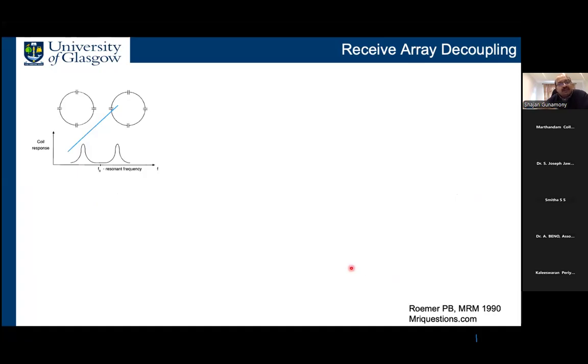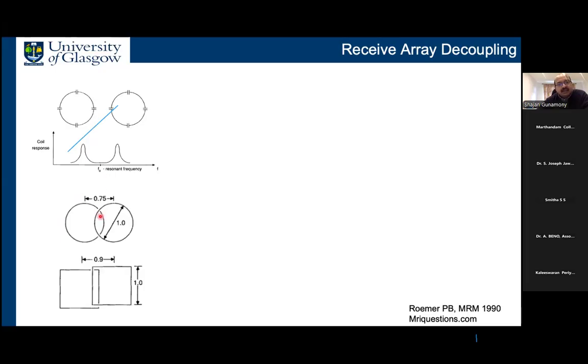So Roemer also proposed a method to build these kinds of coils. As I said, the coils are all resonant circuits. They are tuned to the Larmor frequency. Suppose we have 2 coils. They are tuned to the same frequency. And if you bring them together, they're going to couple very strongly because of mutual inductance. And it will create a split resonance. And at the Larmor frequency, you will have very low signal because the sensitivity is very poor, and the peaks are split.